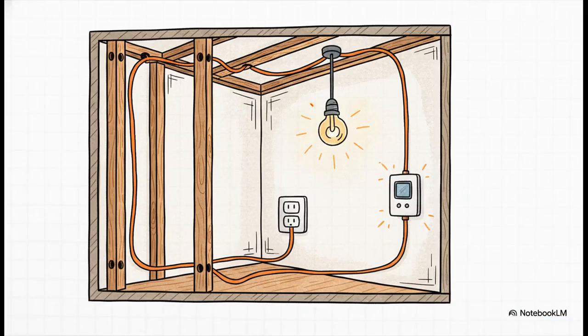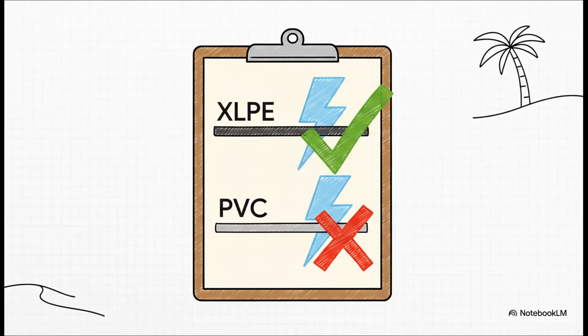But contrast that with PVC's territory. PVC is restricted pretty much entirely to low voltage and extra low voltage systems. But within that specific arena, it is universally dominant. It's the absolute standard for indoor secondary distribution, residential branch circuit wiring, lighting networks, and control systems. In environments where the thermal demands are pretty moderate and being able to bend and route the wire easily is your highest priority, PVC is exactly what you want. And hey, you don't just have to take my word for it. Strict global standards literally enforce this division.